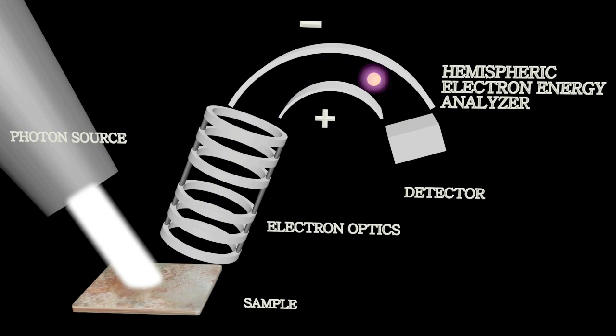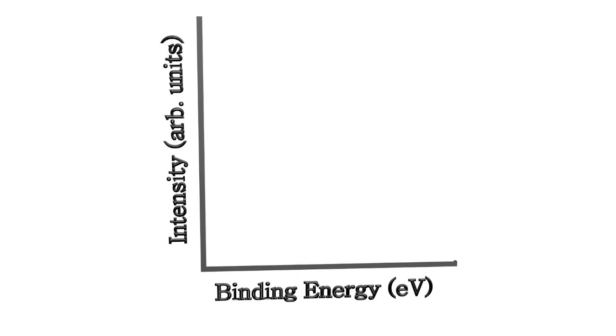In real systems, the Hemispheric Electron Energy Analyzer lets through photoelectrons in a specific energy range. Within this energy window, the precise measurements are done with the help of electron optics that either accelerates or slows down the emitted photoelectrons and then guides them to the analyzer. So the XPS spectrum is obtained by using the electron optics to scan through the energy window that was selected with the Hemispheric Electron Energy Analyzer.